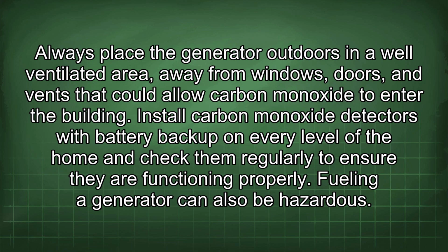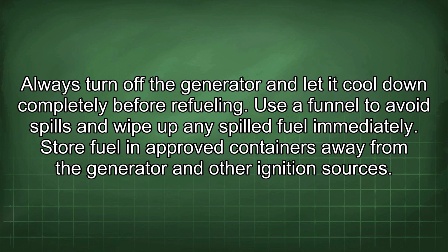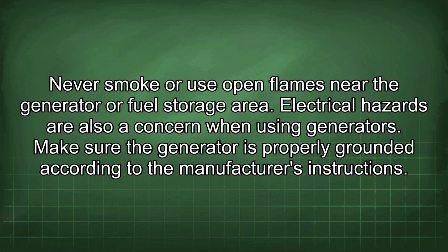Fueling a generator can also be hazardous. Always turn off the generator and let it cool down completely before refueling. Use a funnel to avoid spills and wipe up any spilled fuel immediately. Store fuel in approved containers away from the generator and other ignition sources. Never smoke or use open flames near the generator or fuel storage area.